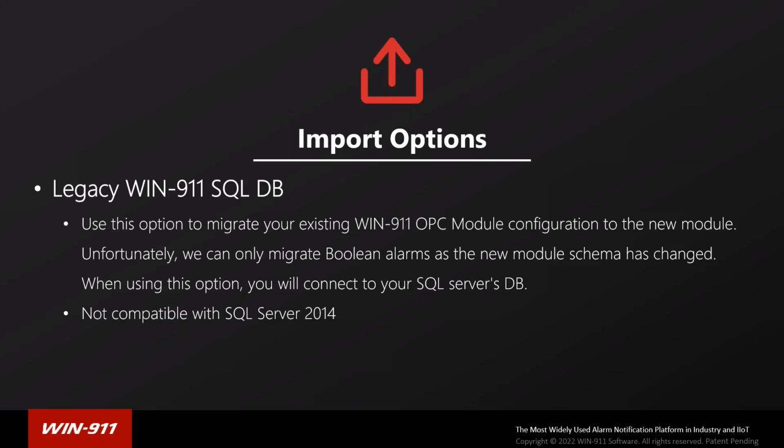Whereas this is only going to be able to convert the Boolean alarms that you have configured in your existing Win-911 configuration. And a special note to mention is it's not compatible with SQL Server 2014. We're using a particular feature of SQL to do this, and we learned after the fact that that feature is not supported in older versions of SQL Server. So if you're using that particular version, then you'd have to take that database and put it into a newer SQL Server, which is not ideal, but unfortunately that's the way it is.